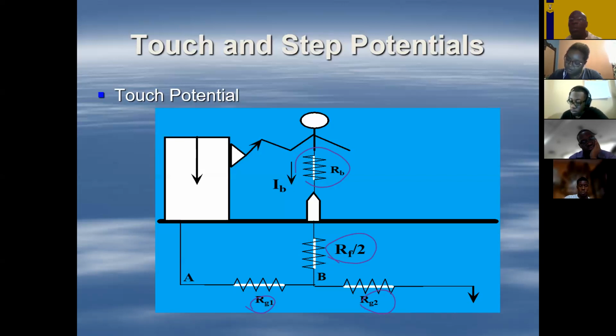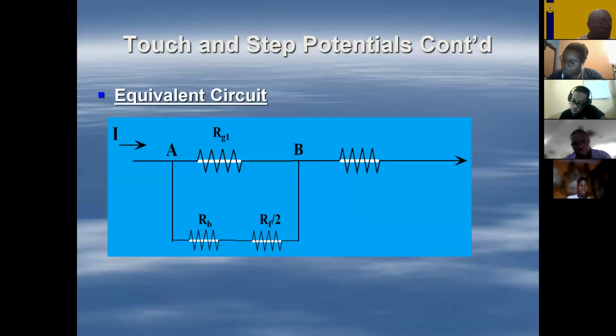It's as if you have separated the resistance up to where the individual is standing, and beyond that, to where we'll have earth fault current. So if this was in place and we're walking around and we touch the equipment, we provide an equivalent circuit to what we have here. And remember, feet are together, that's the assumption, but we know that doesn't happen. The equivalent circuit would then look something like this: we have our RG1, over here would be RG2, here we have the foot resistance over 2 in series with the body resistance of the individual, and the current - we have the fault current there.